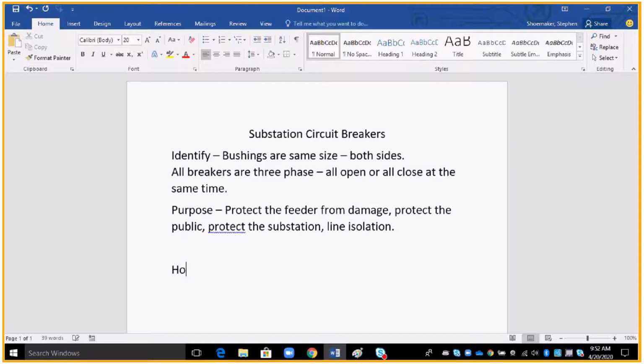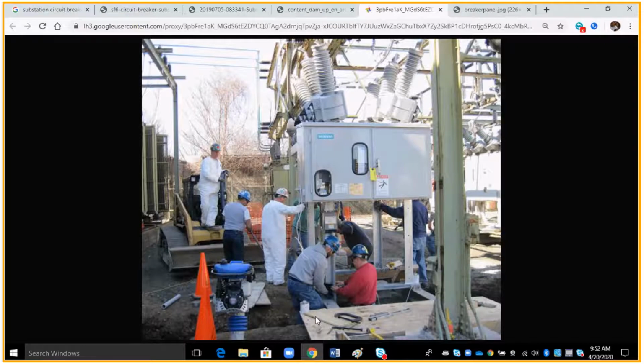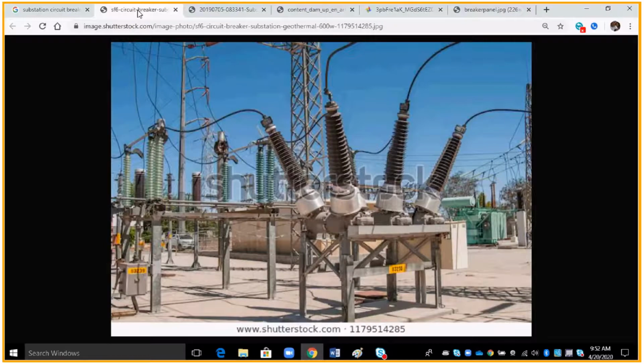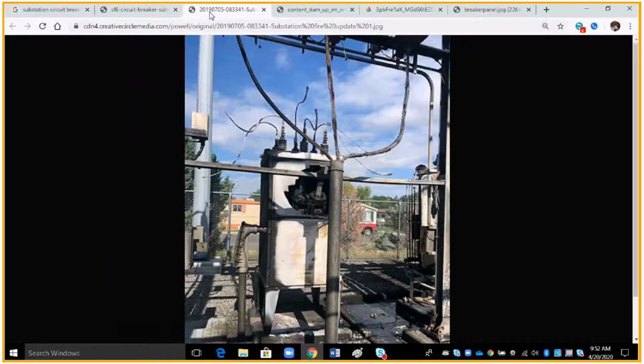How they work. You probably have to go back to your notes a little bit on this one and check it out. Each one of these, and I put up a distribution one to just let you know. I'm just going to go ahead and put my mouse over these areas right here. See if you remember. One side, I have one on this phase, one on this phase, and one on this phase. Look at this next picture. You can't see it on top of the bushing, but it is built into the breaker. You'll see one right here, circling it with my mouse.